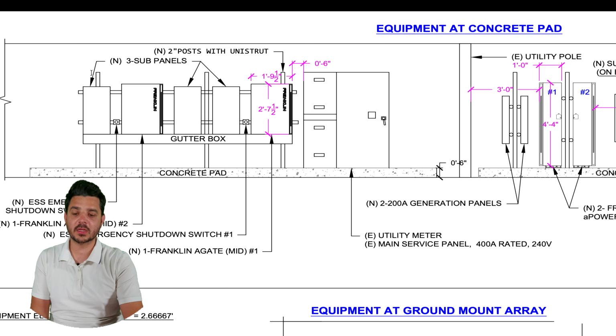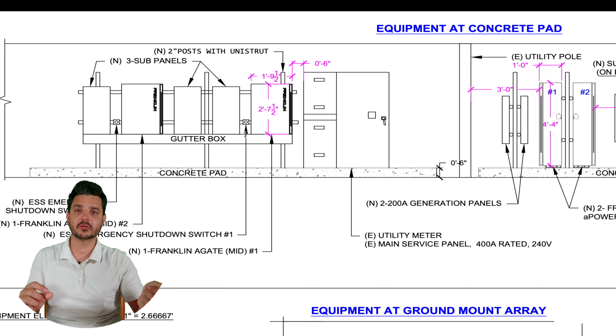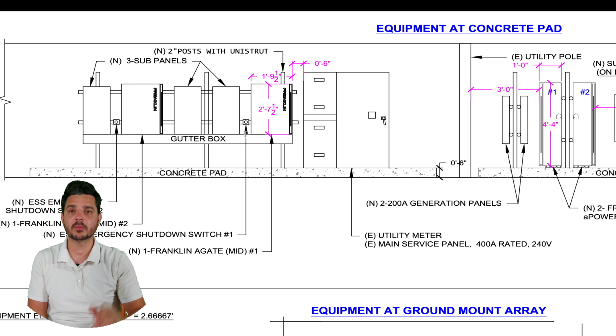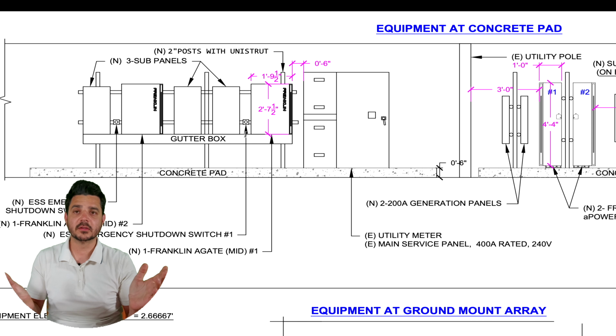This is going to be the generator sub panel. So like I mentioned, the generator's breaker is going to come in, so that'll land here, and then it'll split into 2 100 amps and go to each Franklin aGate, so that way there's generator backup. And then those are the rapid shutdown devices, one for each system. So first responders just turn a little knob or push the button, and voila, the system's off.